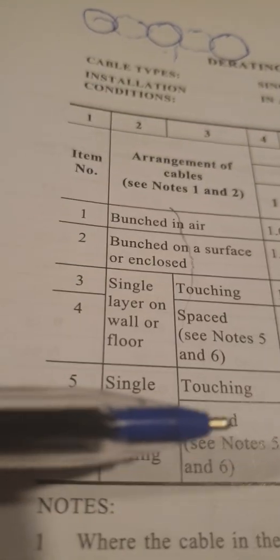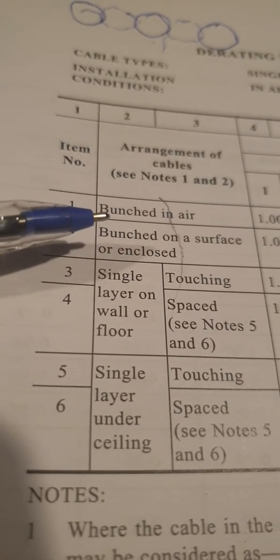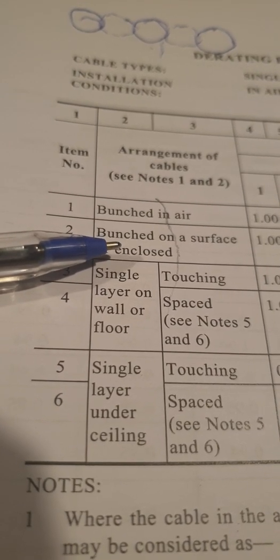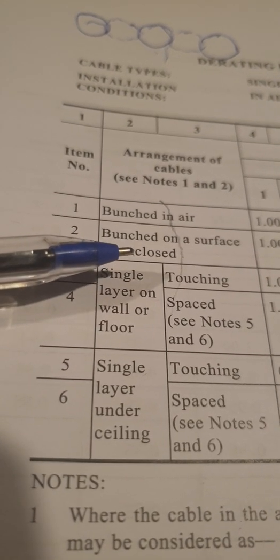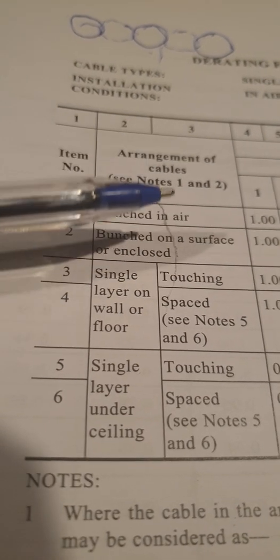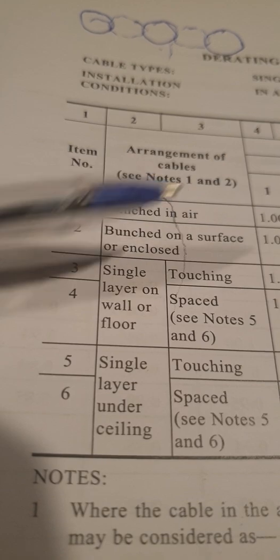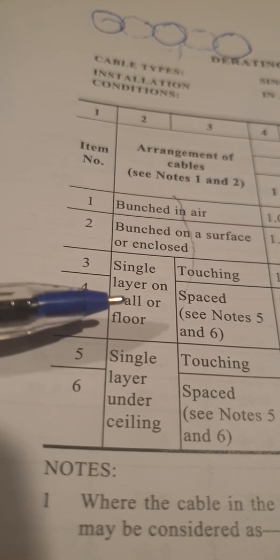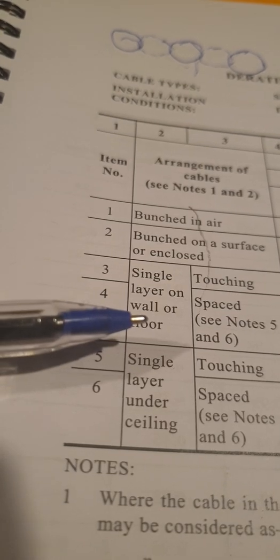Same thing here again - we have touching and we have spaced again for the diameter. Just some simple things to take in there: bunched in air, bunched on the surface, which could be like all the cables joined together, like on a fake ceiling if you have a drop ceiling or something like that, all the cables bunched together on that surface. Bunched in air is more about a catenary.